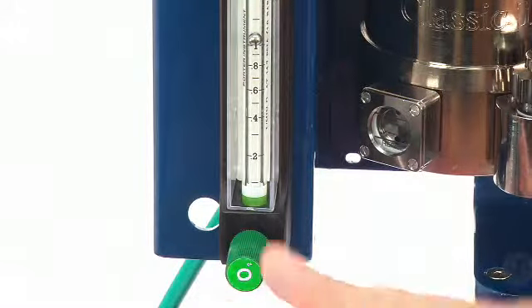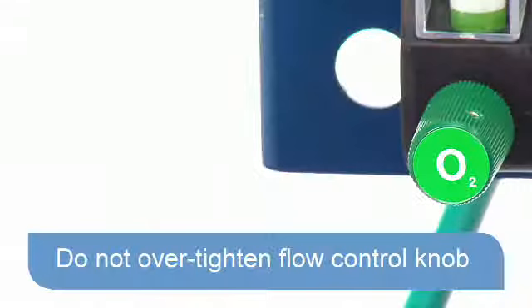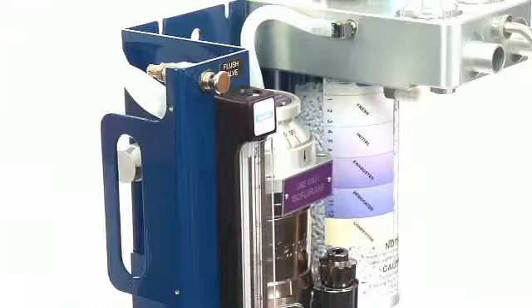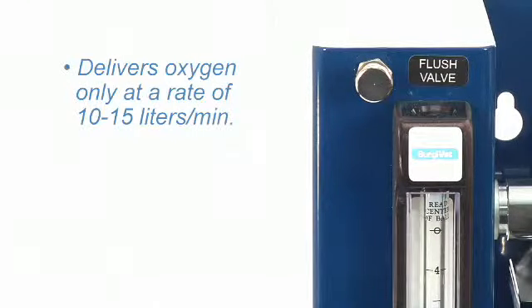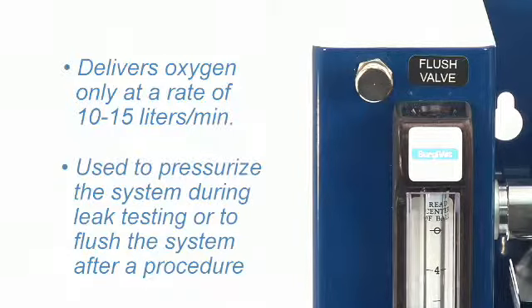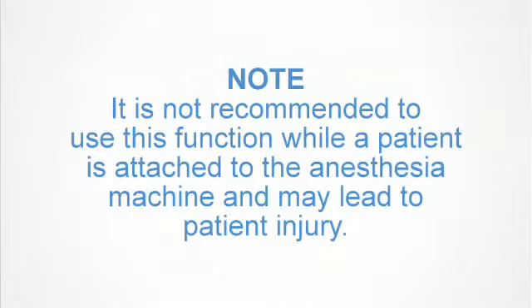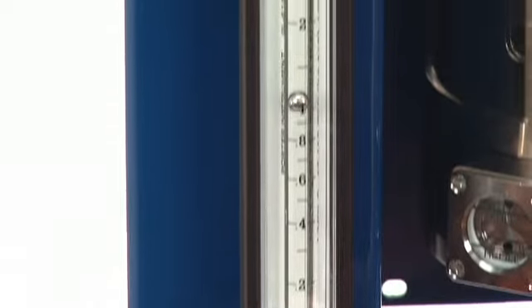The flow control knob should be turned off, clockwise, when not in use. Do not over-tighten, as this can damage the needle valve and torque guard, affecting flow regulation. The oxygen flush valve is located above the flow meter. This button delivers oxygen only at a rate of 10 to 15 liters per minute. The flush valve is used to pressurize the system during the machine leak testing procedure or to flush the system after a procedure. It is not recommended to use this function while a patient is attached to the anesthesia machine, as it may result in patient injury.